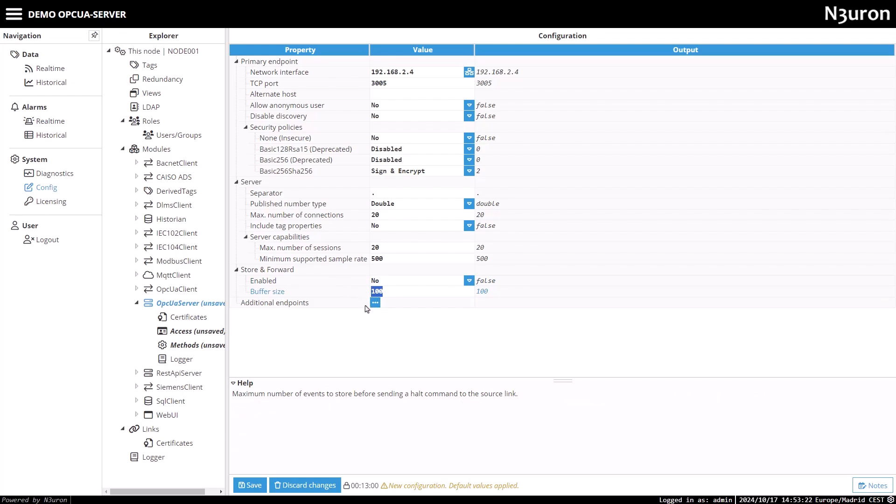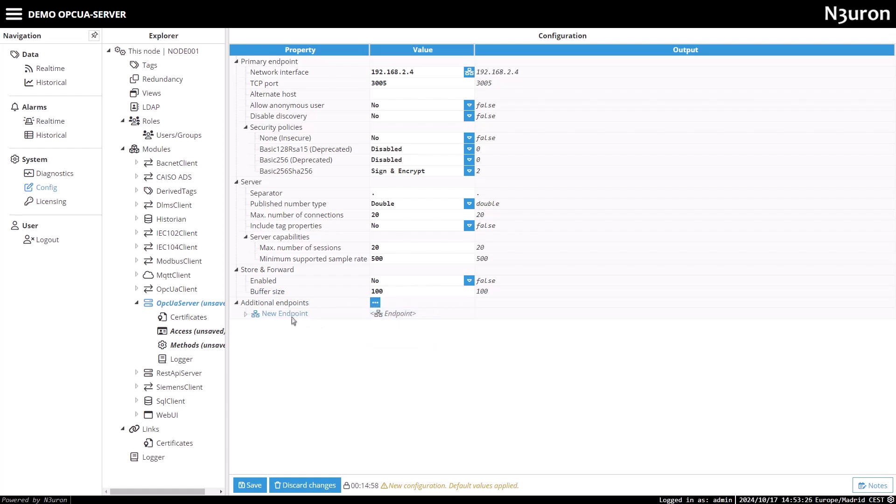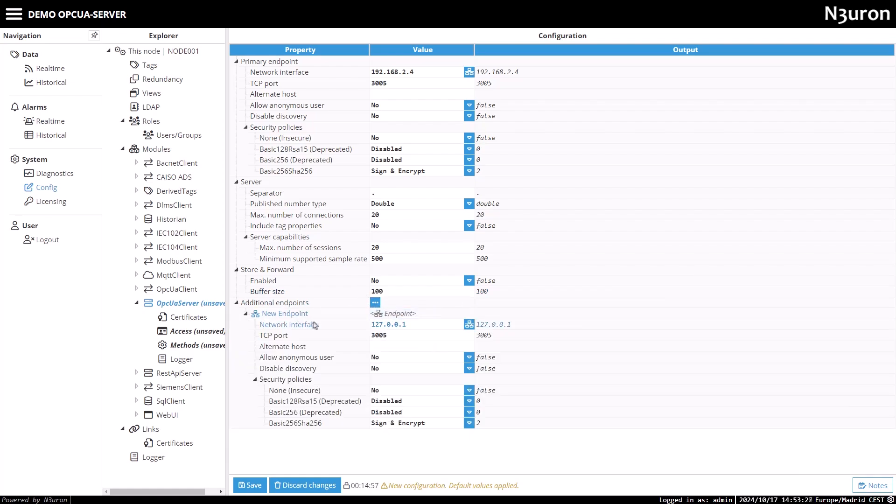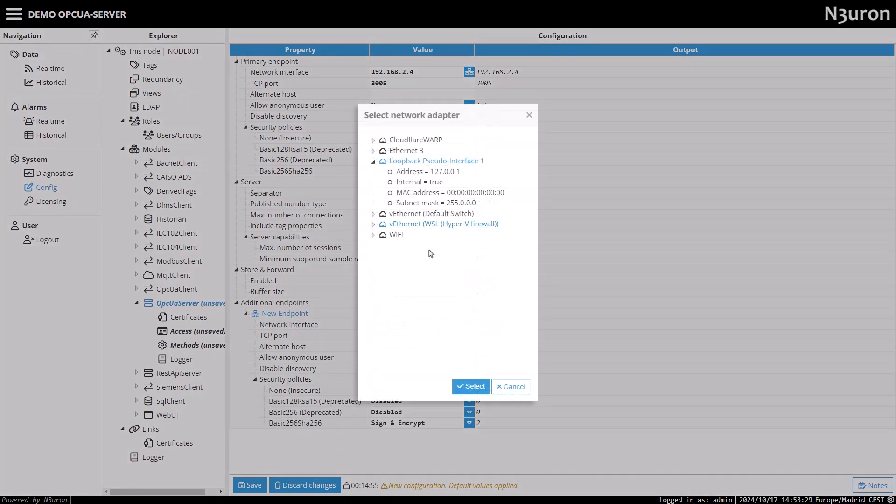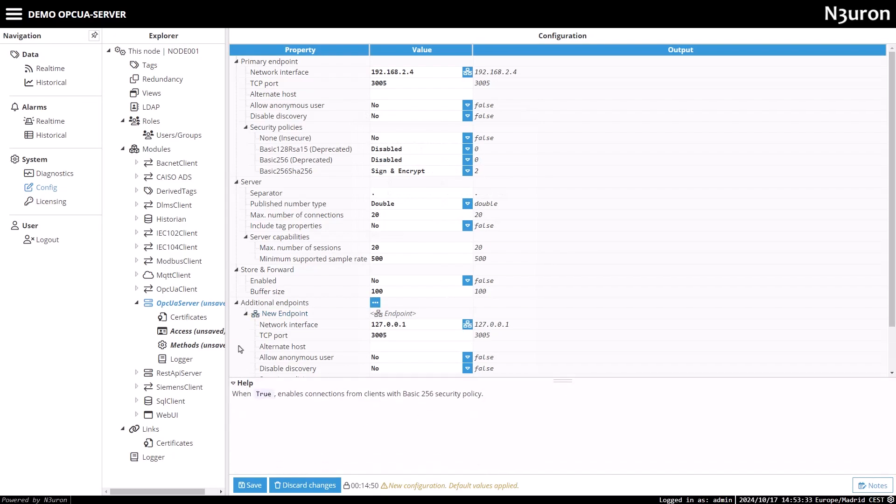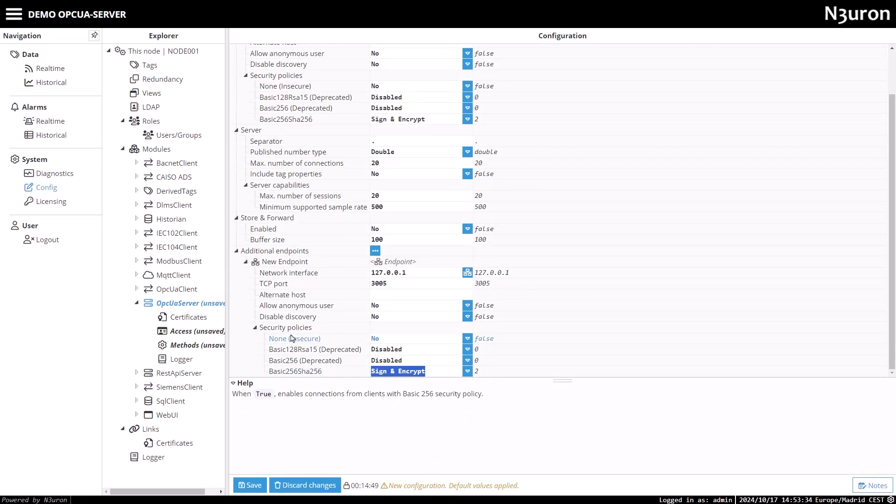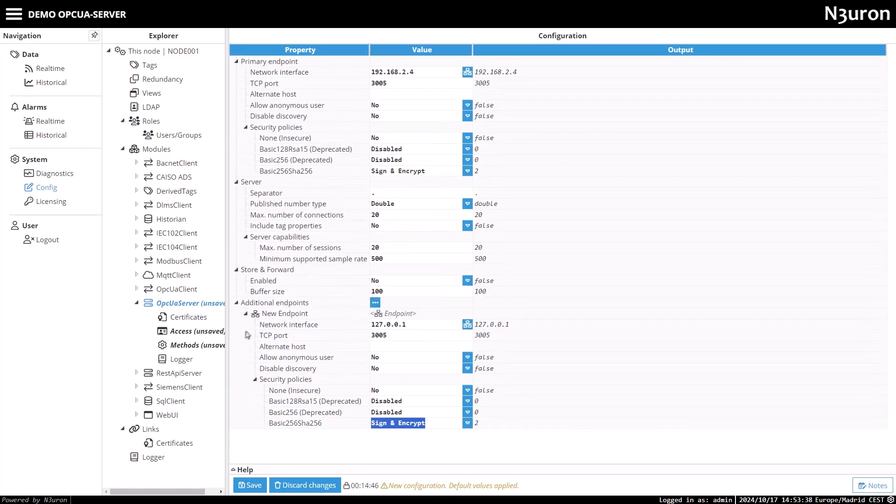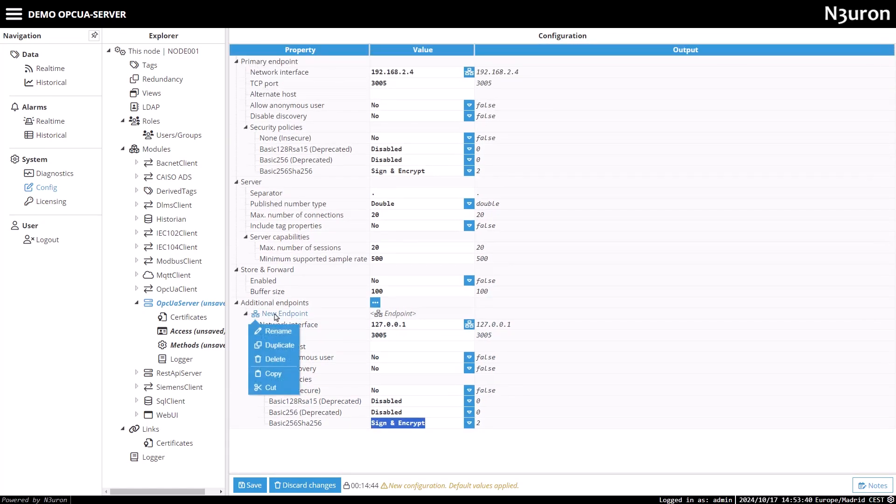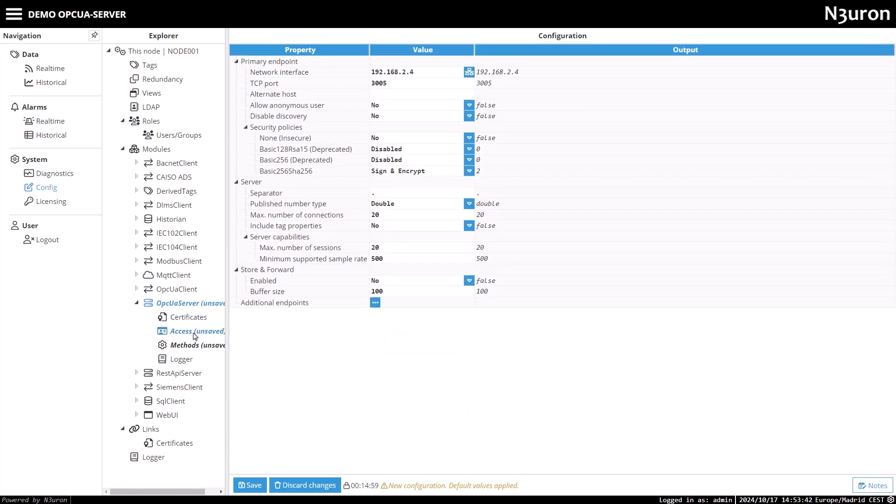We can add an additional endpoint, where we'll configure a separate network interface for incoming connections, including its security policies, just as we did with the primary endpoint. This is necessary when using redundancy, as the backup node will have a different network interface than the one configured for the primary endpoint.